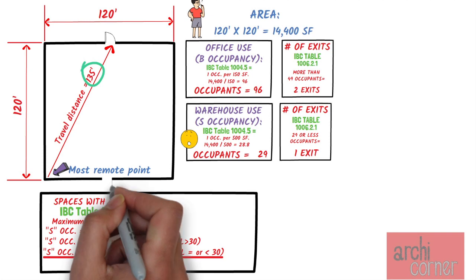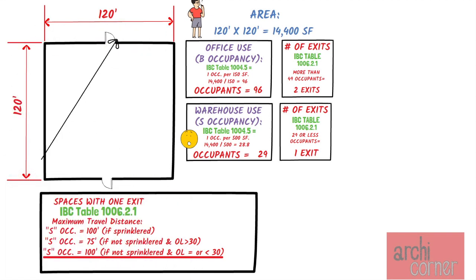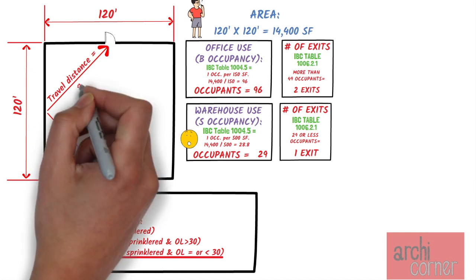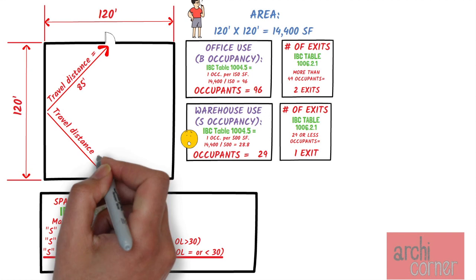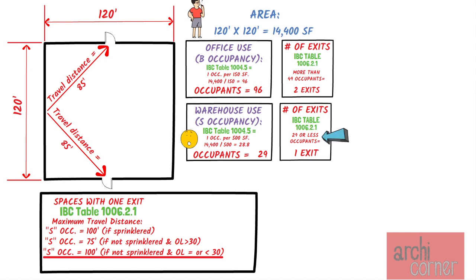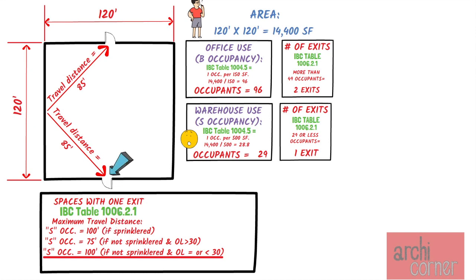To be in compliance, we need to add a door. Adding a door reduces the travel distance so that the furthest location from both doors — the midpoint of each side — is now only 85 feet, assuming nothing is blocking the path. So in this instance, occupant load was not the issue. Based on occupant load alone we had 29 occupants and met the requirement for one exit. However, the second exit was triggered by the path of egress travel distance: IBC limited that distance to 100 feet, but we had 135 feet, requiring the addition of at least one more exit.